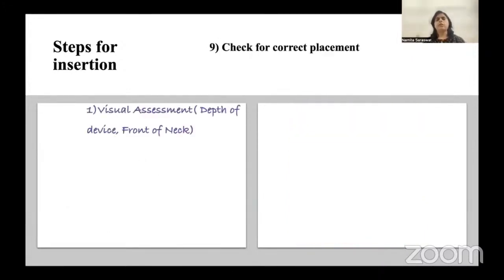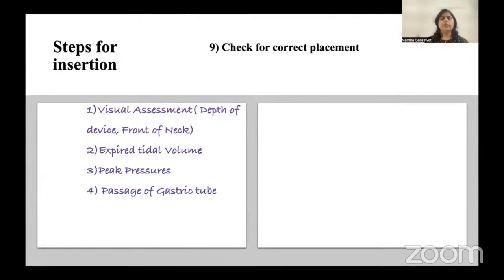After placing the device, the goal is to check whether it has been placed correctly, which can be done in the following steps. First is visual assessment. Look at the depth of the device, which should correspond to the integral bite block. Look at the front of the neck. There should be bulging, which should be minimal and symmetrical. Compare the expired tidal volume with the inspired tidal volume. There should not be much difference between them. Check peak pressures. Passage of a gastric tube is a very good indicator that your device is sitting correctly.